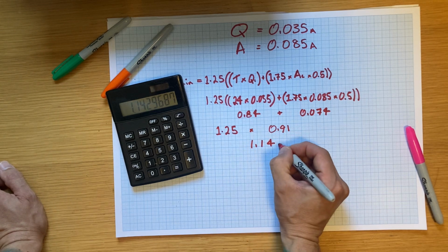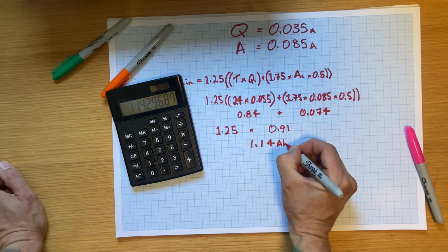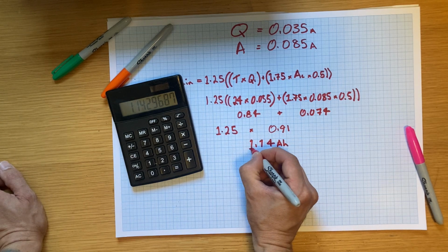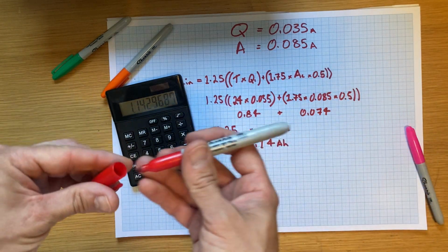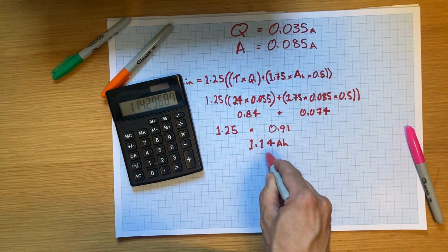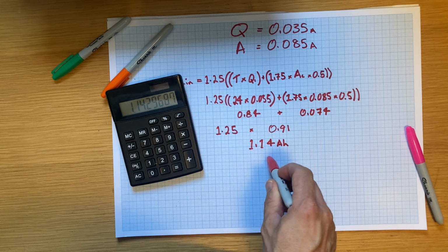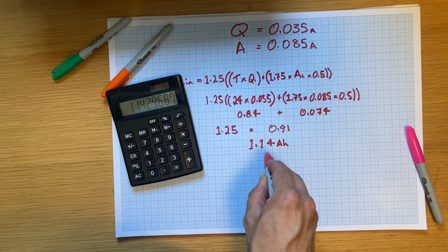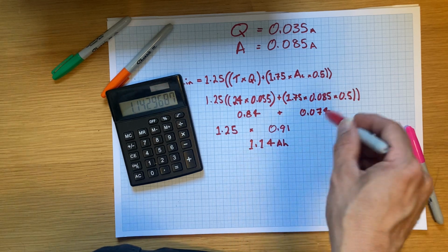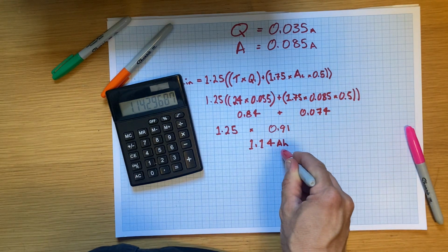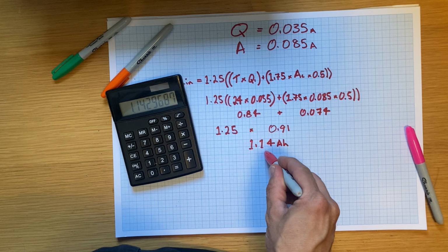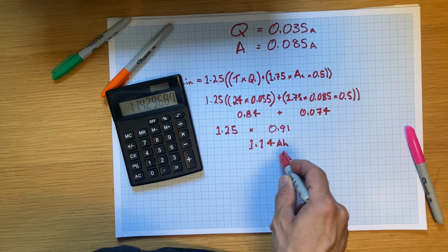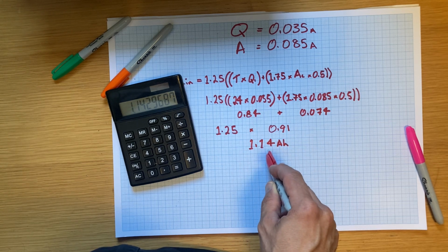1.14 amp hours. So amp hours is obviously how long a battery can run for. So that needs, as a minimum, a battery that can do 1.14 amp hours. What you do is you take that and then just go to the next battery size up. So you're probably looking at a 2 amp hour as the minimum. I'd probably go for that.